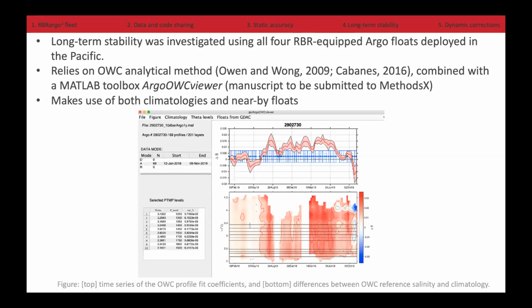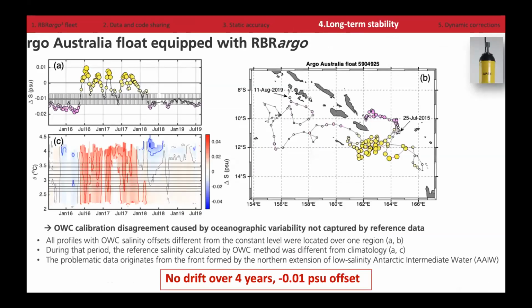If you're interested in reading more about it, I will be more than happy to share the manuscript with you to see how we demonstrate it. But basically, the bottom line is that the drift over 4+ years for some of those floats, actually, this one is a good example. This one was deployed for about 4 years, and there's no significant drift detected over that period of time. This is a float that had a constant offset from the first day due to an initial issue, but the drift is not measurable. What we typically find in the calibration lab is that it should remain within about 0.01 without any need for calibration at all. Often it's 0.005.